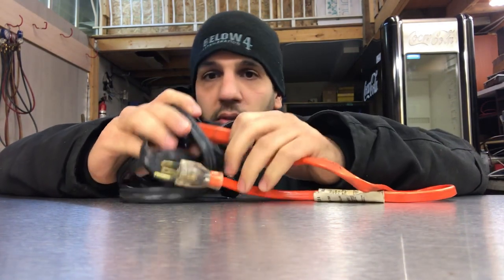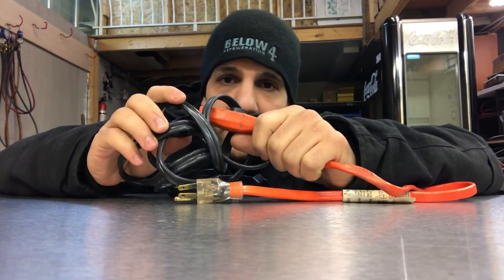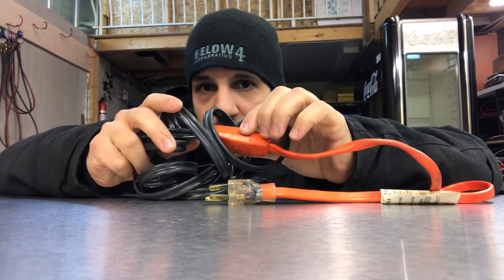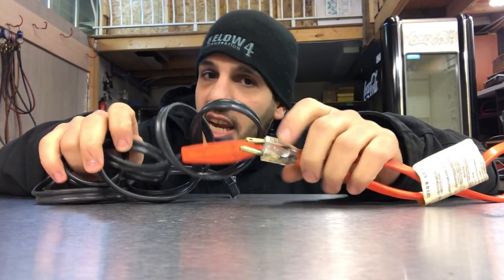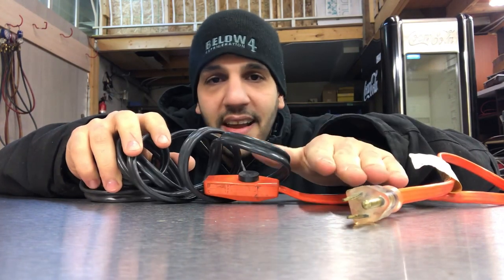So let's talk about the purpose of these trace heaters. These trace heaters are usually found on drain lines inside walk-in freezers. Now I've seen some shady walk-in freezers without these heaters, and all technicians would do is they just put insulation on it. That's an HVAC hack.